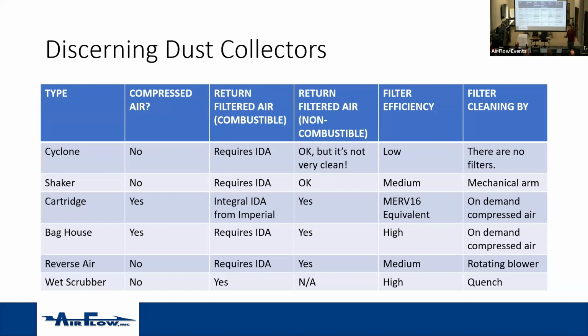Baghouse: compressed air, yes. It requires IDA, just like the rest of them if you're returning it. The return air is filtered. Efficiency is high in a baghouse. You'll see baghouses a lot of times in industrial applications where you have a lot more air and a lot more contaminants that are smaller that you need to filter out. And it also has on-demand compressed air as that pressure differential changes. Reverse air is not compressed air. You'll see that it has a blower itself that will clean it off. It requires IDA. It is filtered, medium efficiency, and there's a rotating blower that goes on it. And we'll see that in the next couple of slides.